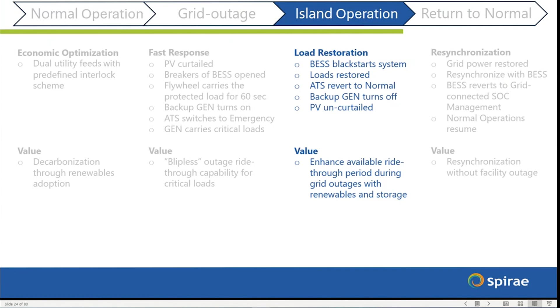In this final part of the demo, we will showcase the resynchronization procedure. Once grid power is restored, a site operator will issue a resynchronization command through Wave. The sync breaker will automatically close once voltage, frequency and phase angle are synced. The battery will transition from grid forming to grid state of charge management, and normal operations will resume.